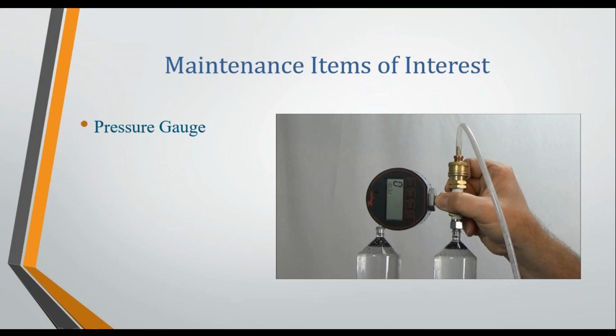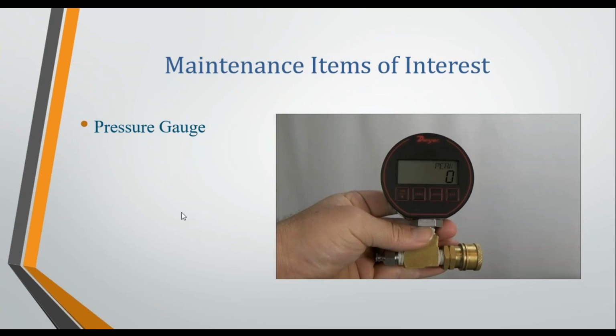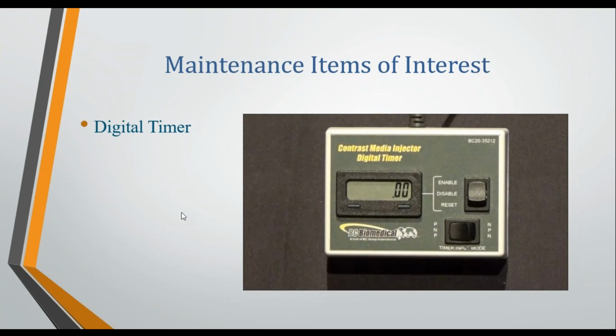And then, like I said, the pressure gauge is always attached directly to the syringe, and that's one of the things that is the problem. Most biomed shops do have a pressure gauge, and they just don't have a pressure gauge that can attach to the syringe. And then finally, the digital timer. As you can see, BC Biomedical, or BC Group especially, makes this thing.